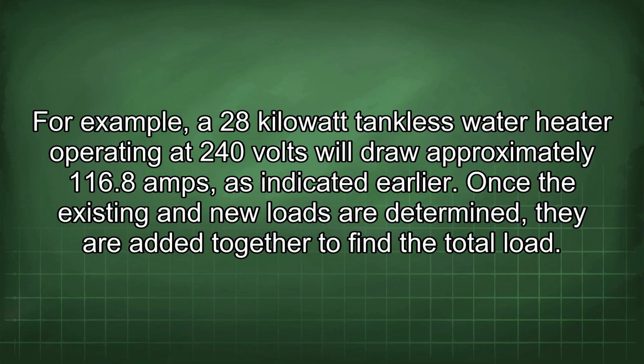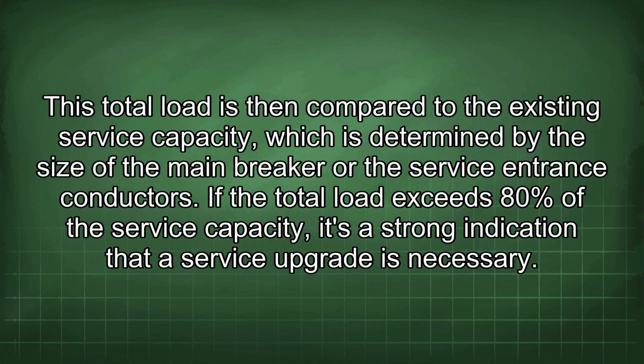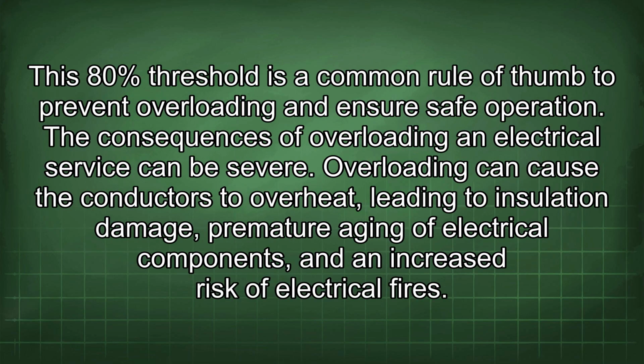Once the existing and new loads are determined, they are added together to find the total load. This total load is then compared to the existing service capacity, which is determined by the size of the main breaker or the service entrance conductors. If the total load exceeds 80% of the service capacity, it's a strong indication that a service upgrade is necessary. This 80% threshold is a common rule of thumb to prevent overloading and ensure safe operation.